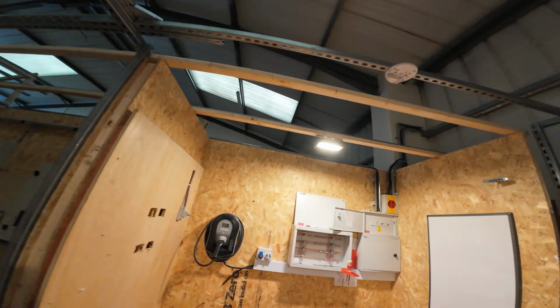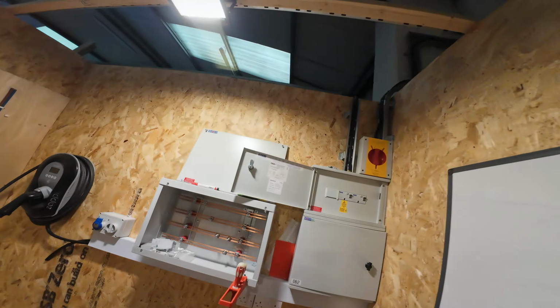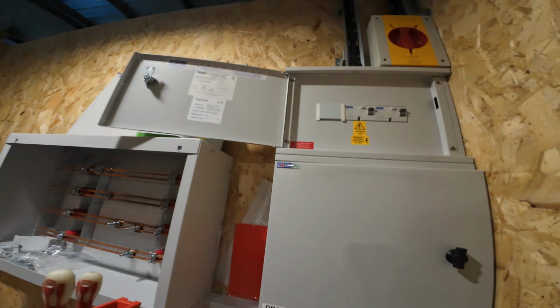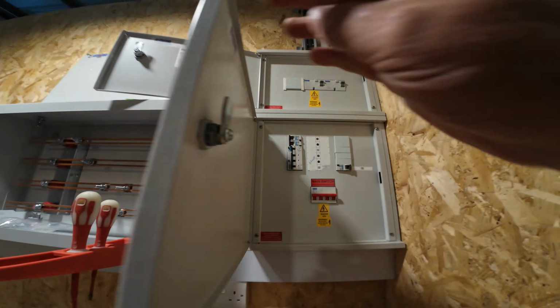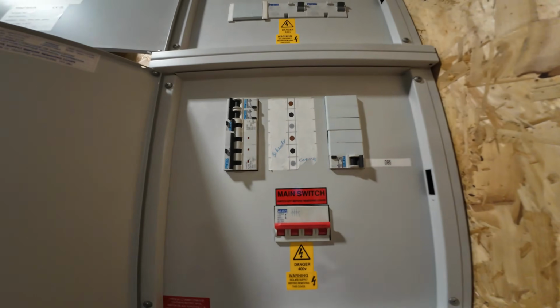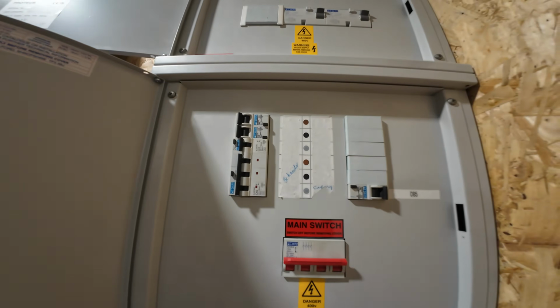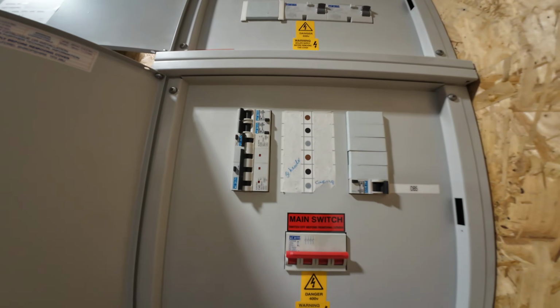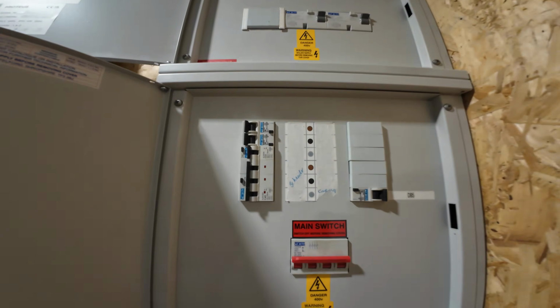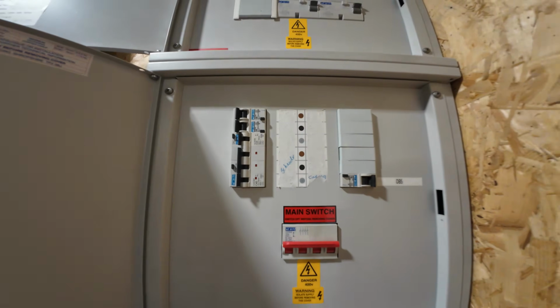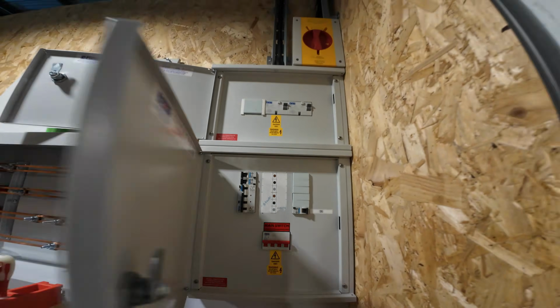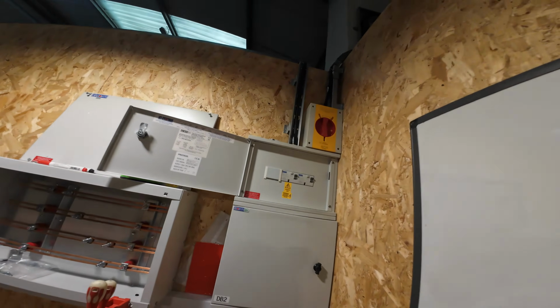What else have we got over in this board? I think we've got some domestic grade breakers in this one. I can't remember if we put them in actually. No, they are all 10 kA rated, so they are still 60898. However, they are 10 kA rated, and that's just for your commercial environments where your fault current's typically higher.